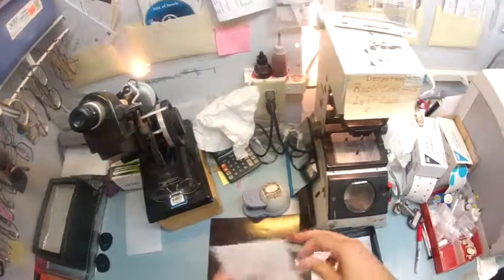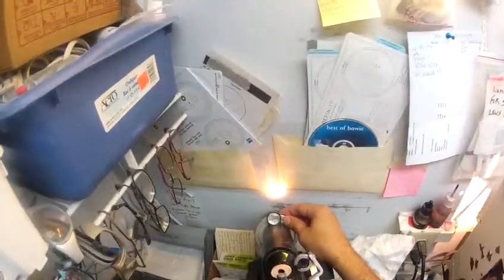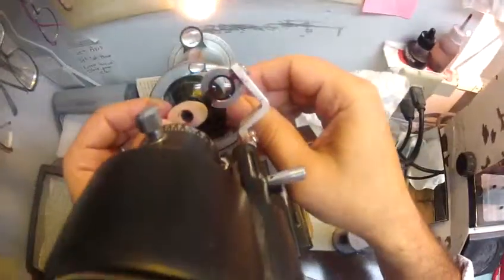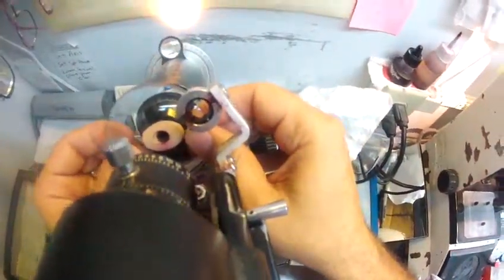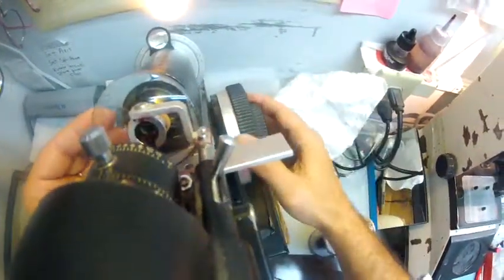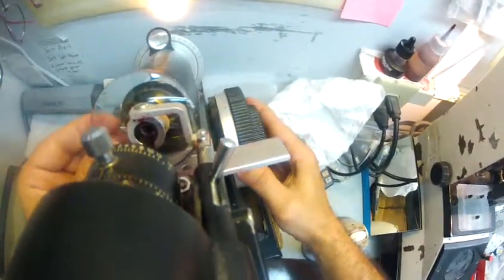I'm going to take both your lenses out of their protective sleeves. This is your right lens. I've still got the axis wheel set at 178 on my Marco 101 lensometer. I'm going to spin the power drum to 4. I'm going to put your lens in and rotate it until the sphere power comes in clearly. Dead center there. Let me check your astigmatism correction. A little high, so I'm going to lower the lens. I have a little platform here that raises and lowers. I just want to get everything perfect. Perfect!